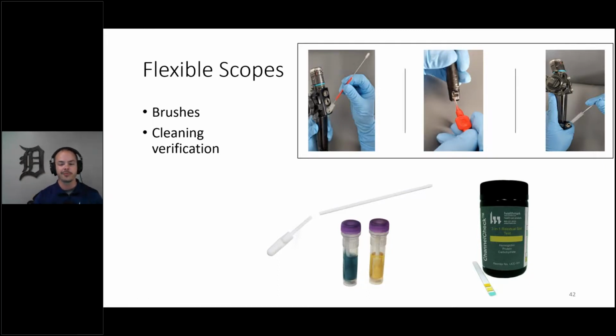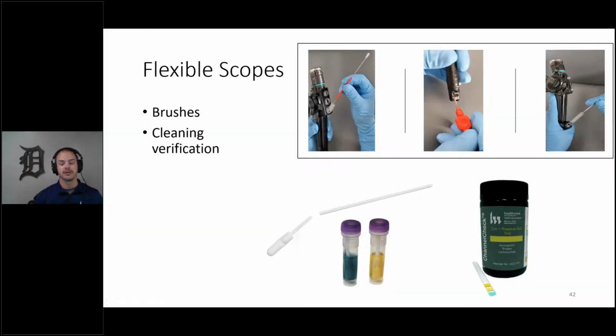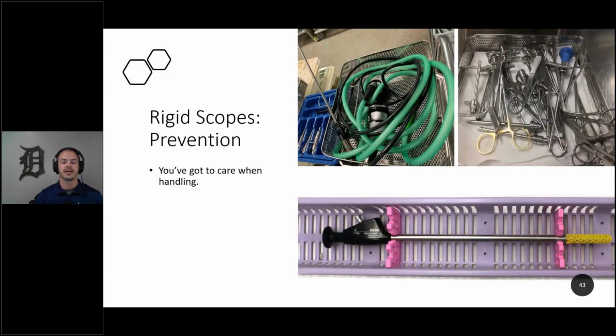Are we going to think about putting cleaning verification into our process? This is really important because we could even be following the IFU and maybe have a bore scope to inspect these devices, but maybe we don't. If we don't, this cleaning verification tool we can implement after our manual cleaning procedure could potentially identify problems with our cleaning process. Many times, failures in a cleaning verification test lead users to find out their endoscope was damaged. So these cleaning verification tests are very valuable to implement in your process.